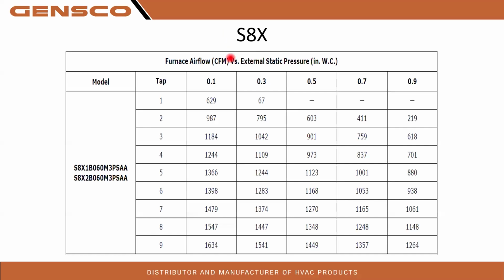Here's our S8X1. This one is out of the 60,000 BTU. Everybody knows S series are the shorties, 34-inch tall. 8 means that it's an 80%er. 1 means it's a single stage. 2 is a 2-stage. We got a 60,000 BTU, 3-ton blower motor. So at 0.5 design static pressure, we change these taps through the menu select buttons on the circuit board. Tap 5 default is 1123.